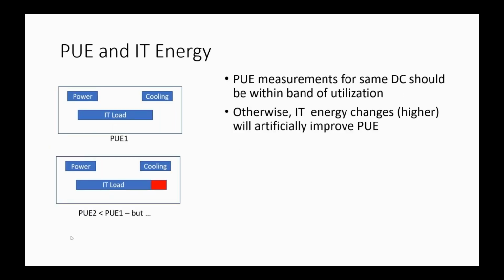So Mohan, the red is not reported? No, so I just crank up the load. Let's say you say, Mohan, I need to report PUE for our data center at Intel. I say, okay, I'm going to put a huge load on the IT for the next couple of days. Let's go ahead and measure it. Because your denominator is higher, your PUE comes out lower. Okay, got it. It's how much the load changes efficiency. Exactly.